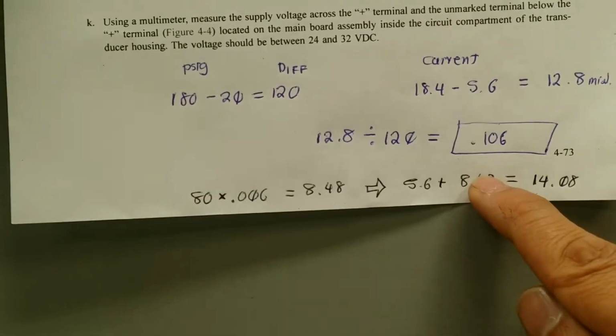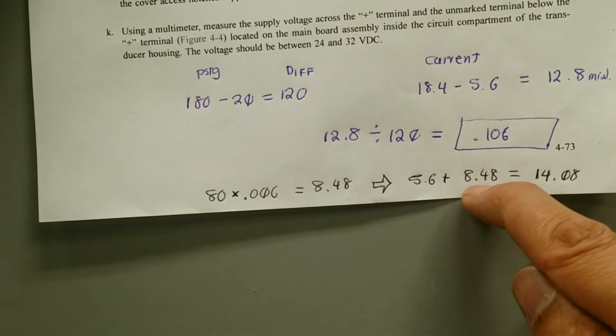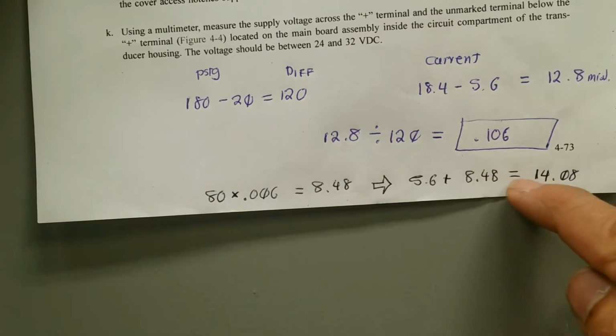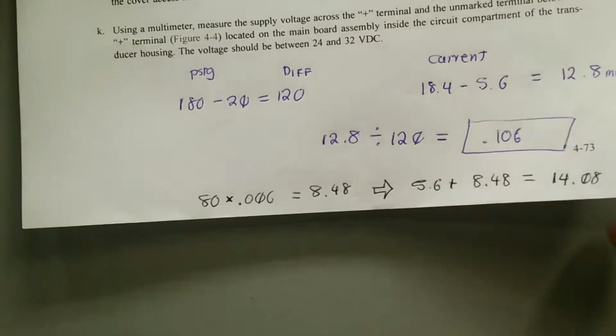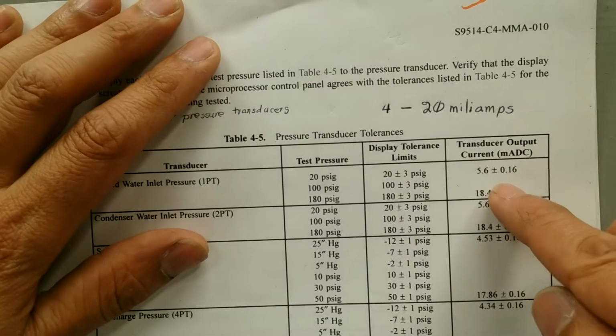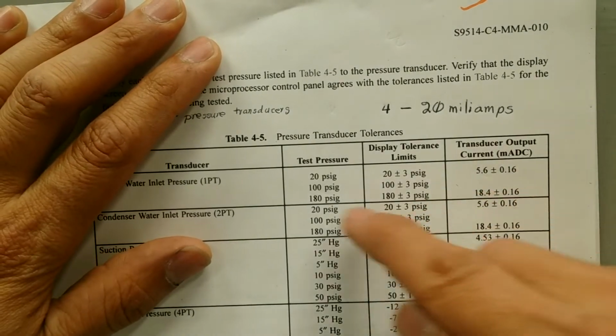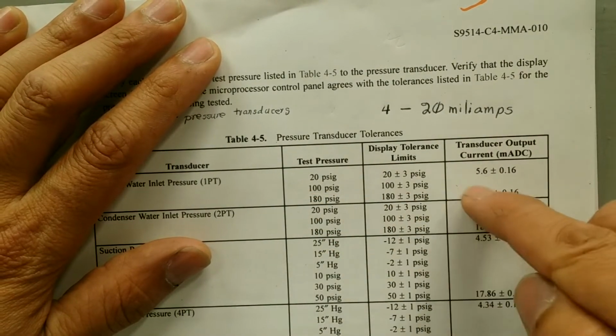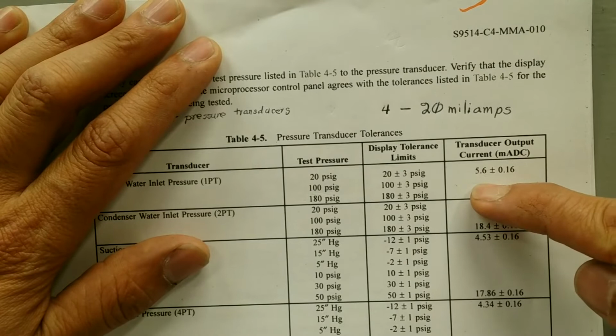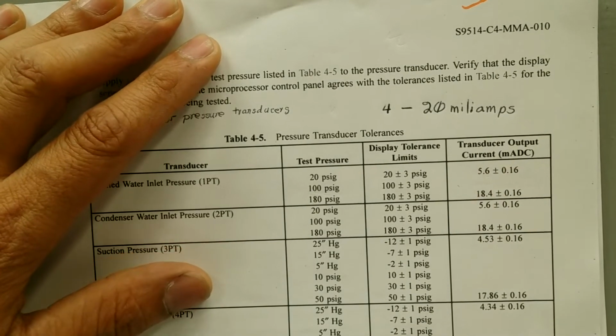This is actually a 5.6. This is your starting value. So 5.6 plus the difference, 8.48, gives 14.08 milliamps. So when it is 100 psi, here it should be 14.08 milliamps.